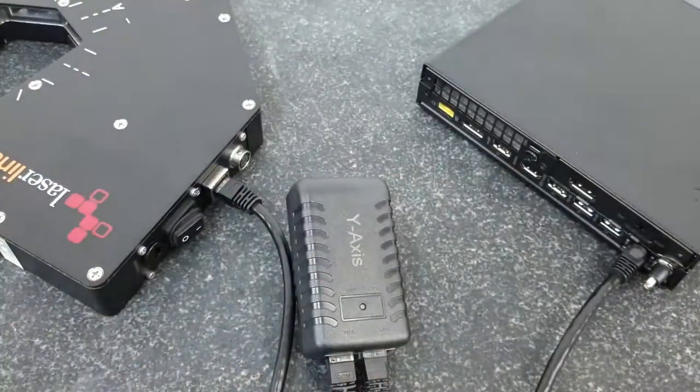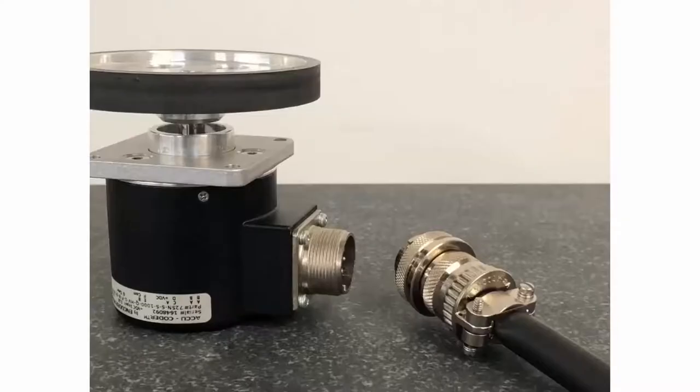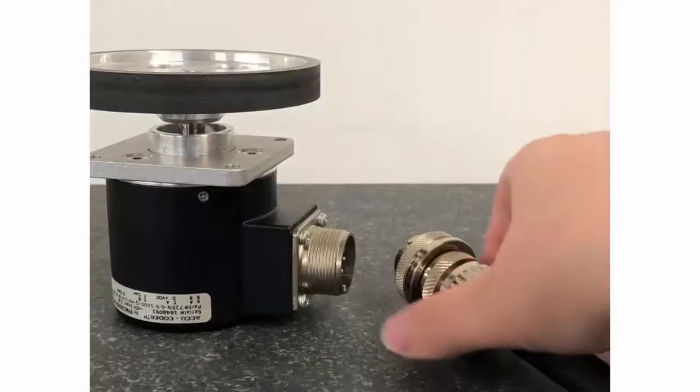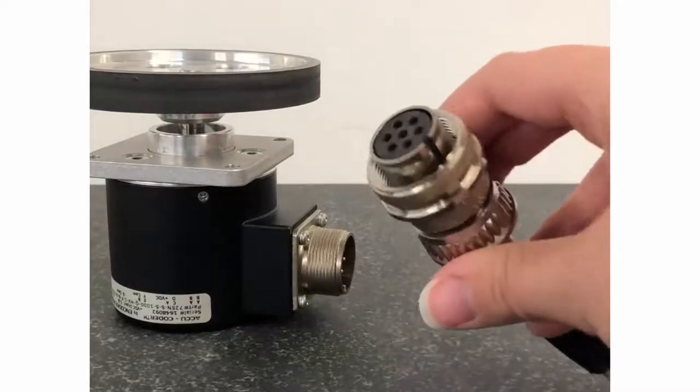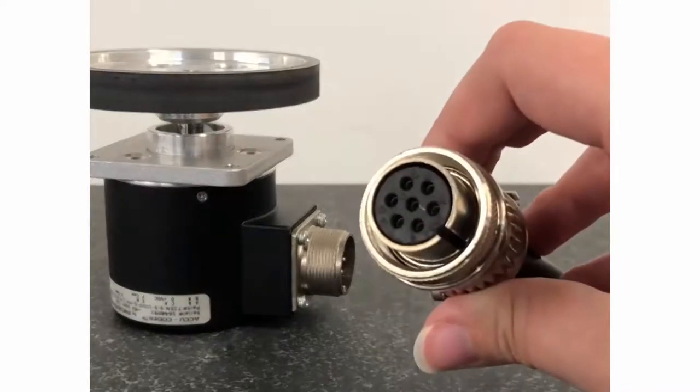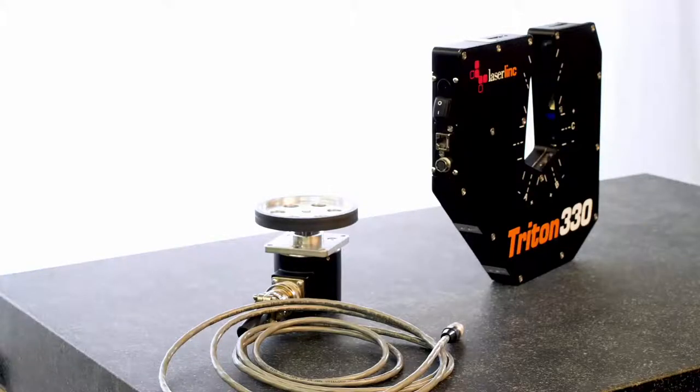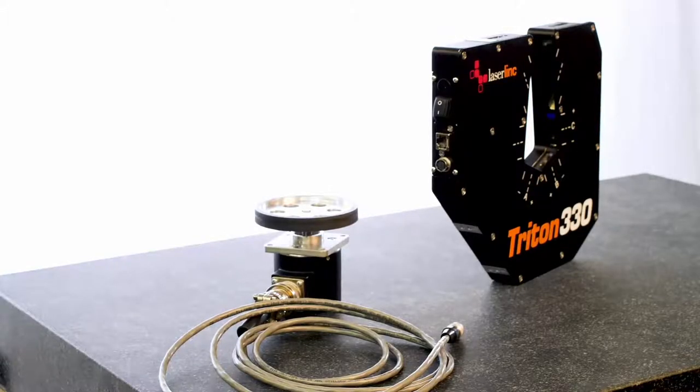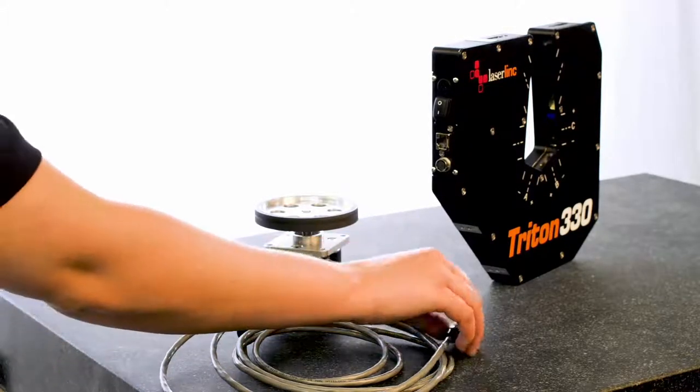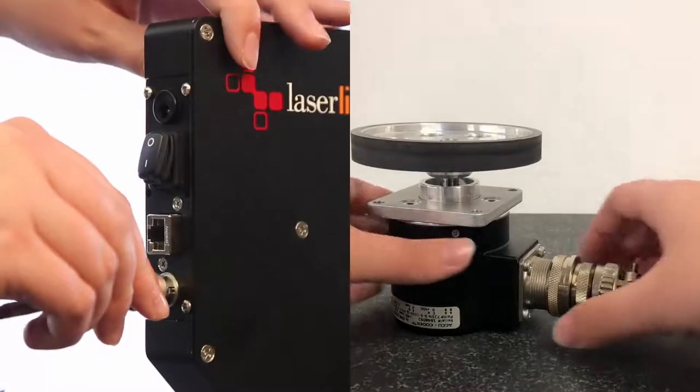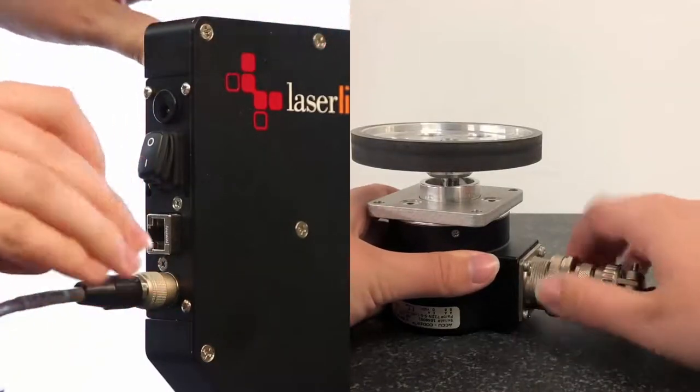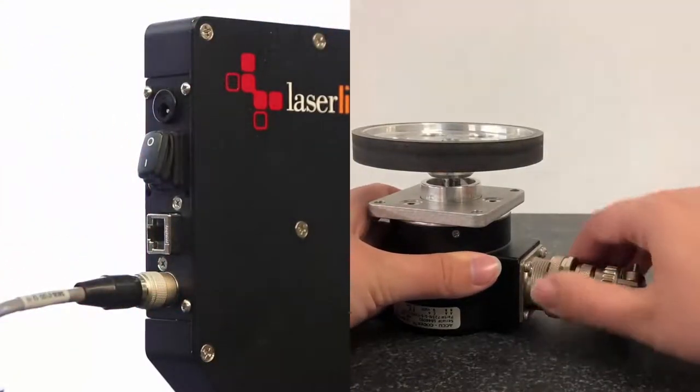Next, we will connect the encoder cable to the micrometer so that the software can track the length of product running through the gauge as measurements are taken. If using an encoder wheel, you will need a cable with a crown connector like this at one end and a Hirose connection like this at the other. Connect the Hirose end of the cable to the micrometer and the crown end of the cable to the encoder.